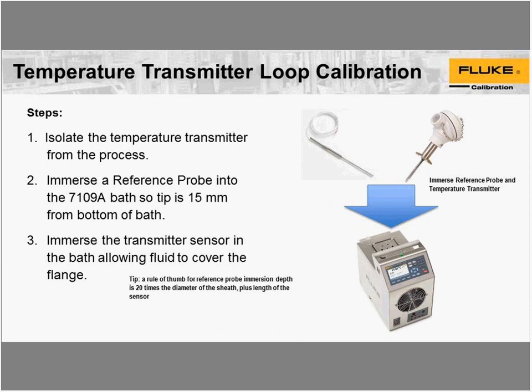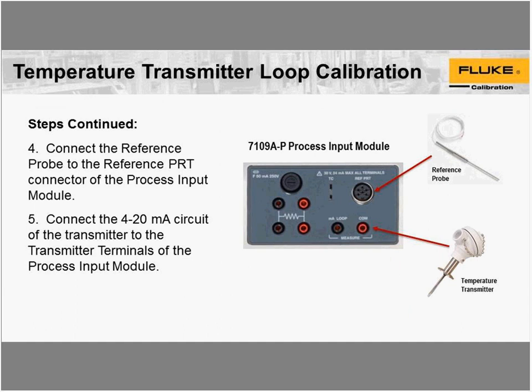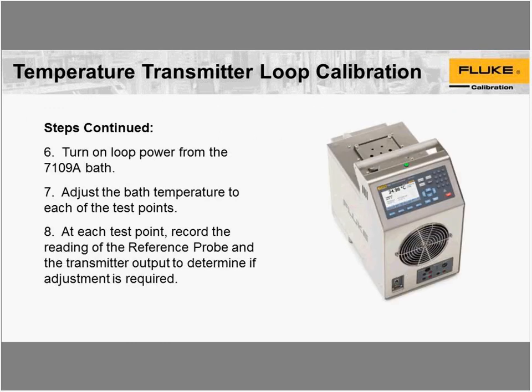All right. Let's see. I think we've already covered inserting the sensor into the bath. You connect the transmitter to the 4 to 20 milliamp circuit, and from there, if the transmitter has its own power source, then you can turn on loop power. There's a feature that the 7109A has. It will power the transmitter if you need that. Otherwise, if it's already powered separately, then you can turn loop power off in the 7109A bath.